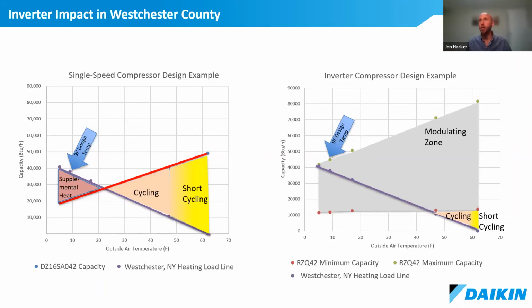So this is an example home in Westchester, New York. Again, similar graphic, we're showing loads and capacities on the y-axis and outdoor temperatures on the x-axis. On the left-hand side of the slide, we're showing a single speed product. It's the same exact single speed product with the same exact capacity line, but it's shown in red now. And the example house load that we've got is shown as a purple line. The design condition for this location is 9 degrees Fahrenheit. And you can see that the heat load line basically goes to 0 around 62 degrees Fahrenheit. So at that point, you don't really need heat anymore.